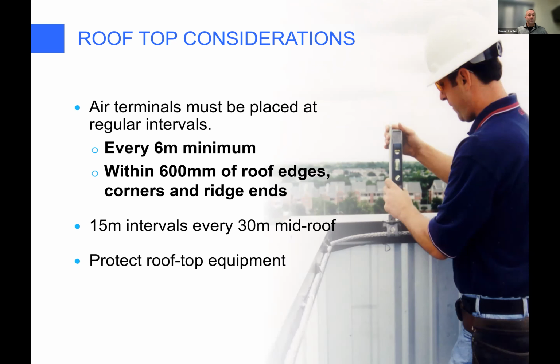So all that said, where do the air terminals go? Well, they have to be at outside edges and corners. Those are statistically likely places for counter leaders to develop, so it's a good place to have a lightning rod. 600 millimeters is the number you're looking for, distance from an outside edge or an outside corner.